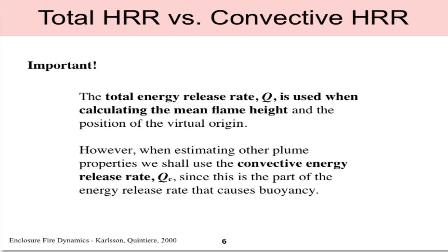Before we do that, I'd like to make the distinction that the total energy release rate Q should be used when calculating the mean flame height and the position of the virtual origin. Otherwise, when we estimate other plume properties, we'll use QC, which is the convective heat release rate. Typically, for most fires and for this course, we will assume that the convective energy release rate is 70% of the total heat release rate. This is true for liquid pool fires and most cases.